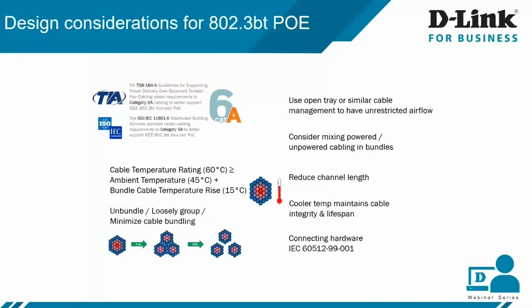60512-99-001, to have uninterrupted performance. Even some vendors have increased the temperature rating - previously if my keystone was rated 60 degrees Celsius, now it is 65 degrees Celsius. So when using type 3 or type 4, we have to consider the atmosphere, what type of bundle or how many cables we are using in the bundle, what category of cable we are using, and whether my connector hardware is compliant to IEC standard. All these things, and then following the TSB 184 installation guideline, are very, very important.